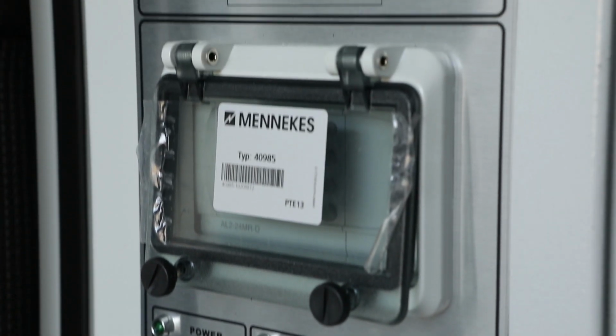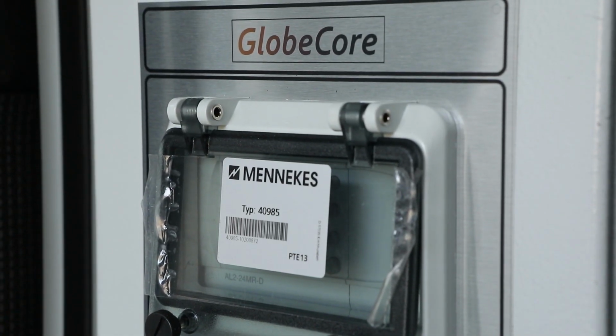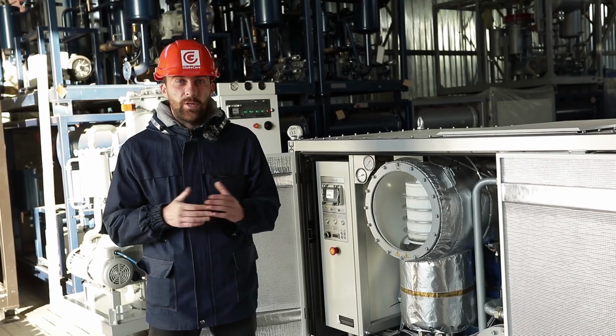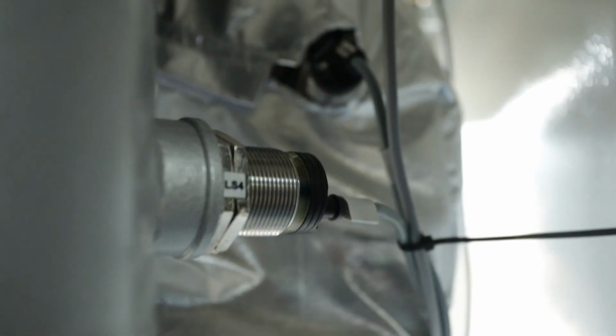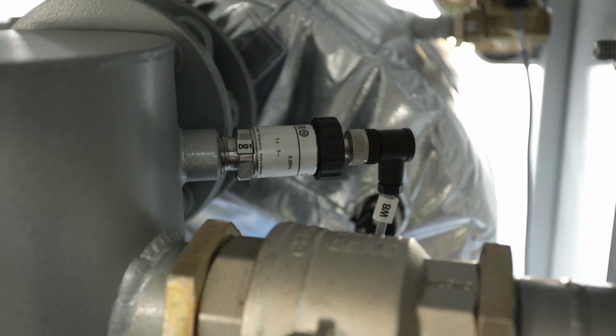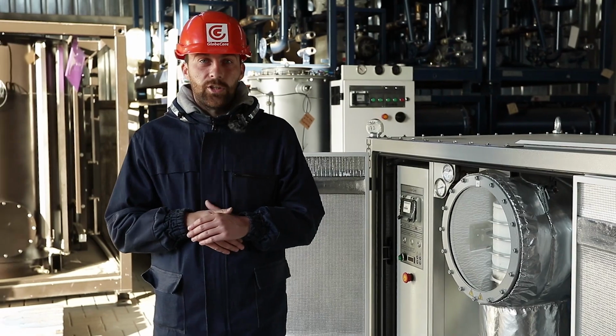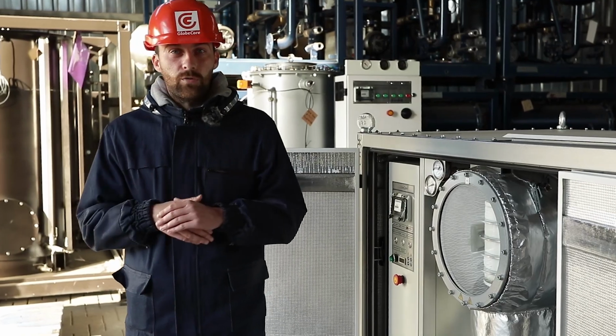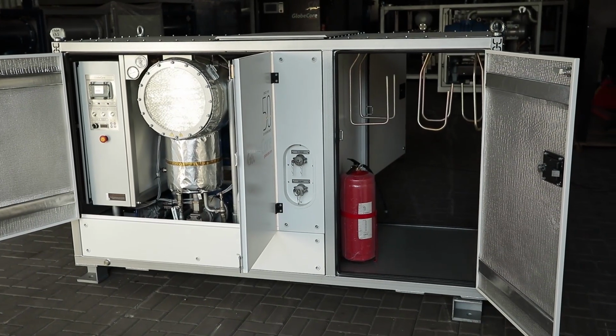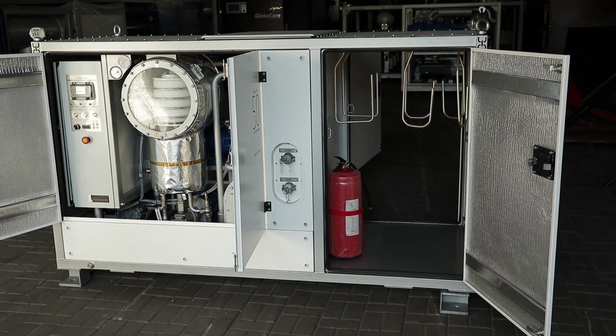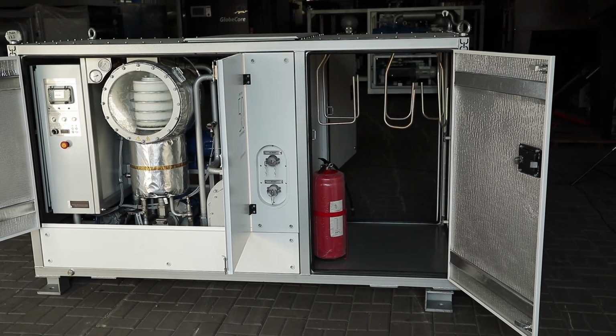The safe operation of the unit is ensured by the presence of oil level sensors, an oil spill sensor in the tray, a foam sensor, and a sensor for presence of oil in the trap that protects the vacuum pipeline. In order to enhance the operation convenience of the equipment, we have added a separate compartment for storing tools, hoses, and other accessories. The container has been wheeled, so the unit can quickly move from one work location to the other.